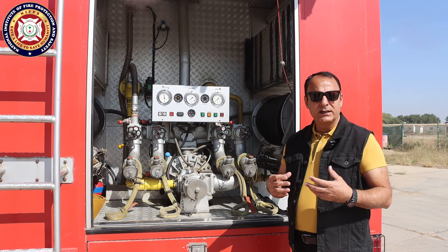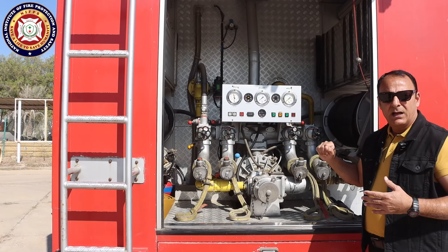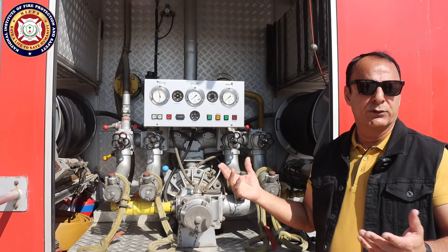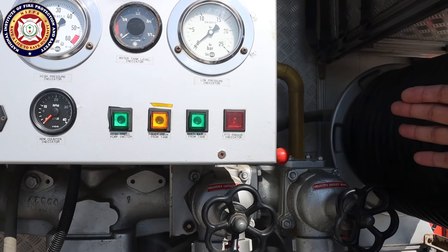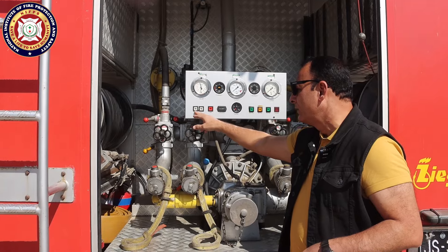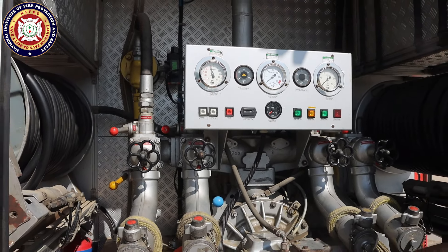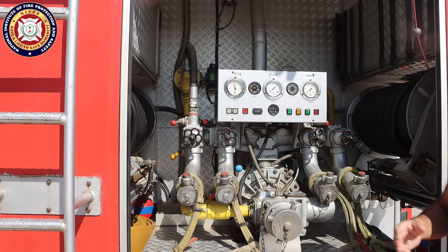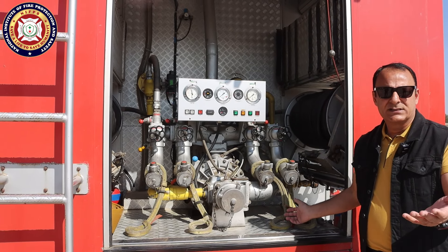To operate: we have a Ziegler pump and the water tank at the back. We open the water tank using a pneumatic solenoid-operated valve. Pressing the button automatically opens the valve and water immediately enters the pump. Once water comes in, I increase the RPM above 5 bar. There are four individual water delivery outlets. We connect the hose to a delivery outlet — a hose holder prevents the hose from disconnecting unexpectedly.